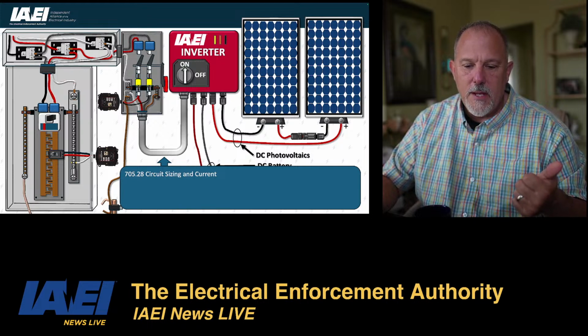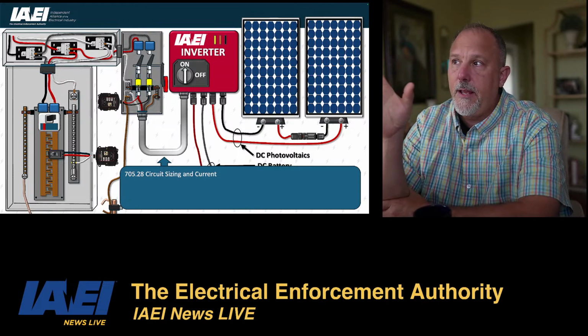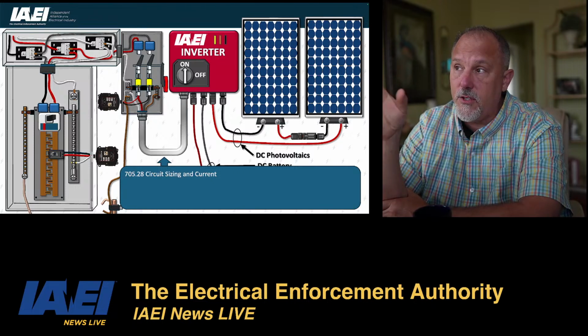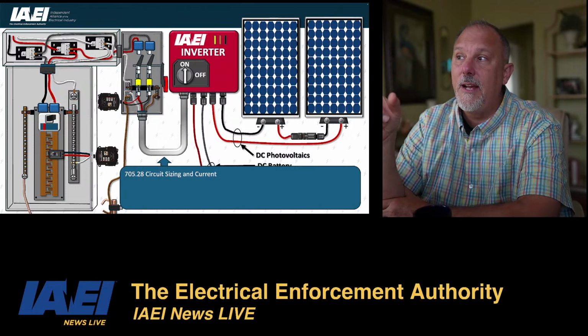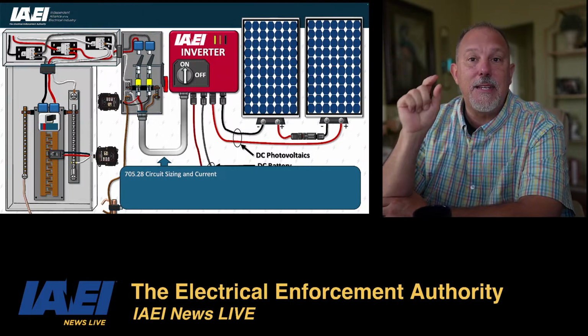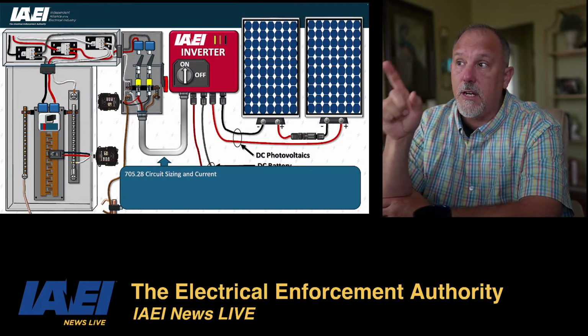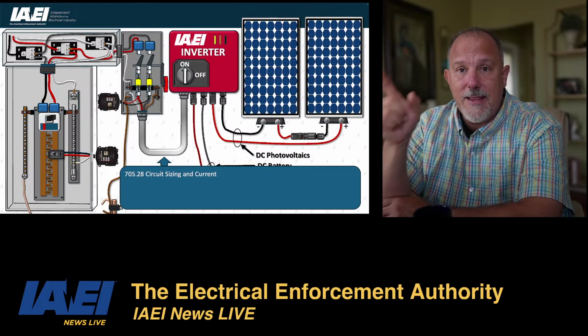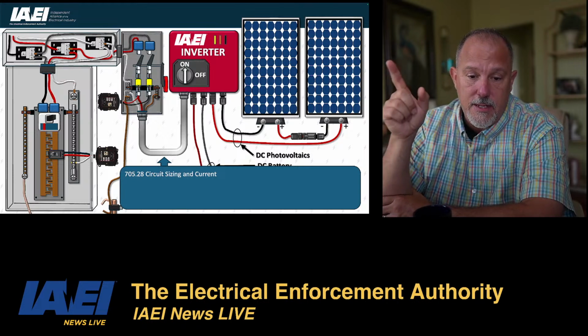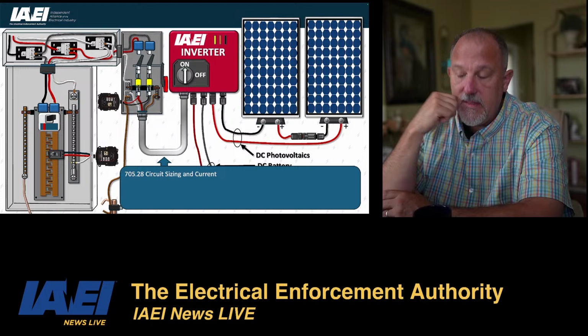But the inverter is still the control device. Does that not make it part of the service equipment? Again, no. In this case here, it is a feeder. So that's not service equipment, because that disconnect is not disconnecting service conductors. The service conductors stop at that AC disconnect switch in this image. All right.